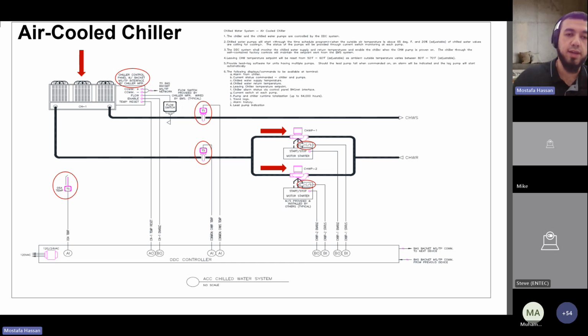That's a great point there. It's directly indicating that this is provided by the chiller manufacturer. You don't need to go ask around. You don't need to send in an RFI to the designer. I'm talking as a controls contractor. If I'm estimating this, for example, I don't have to send an email to the engineer, because it sits right there. The BACnet interface is coming through the chiller manufacturer, so I know I need to run a communication point back to my DDC controller, which is shown down here.